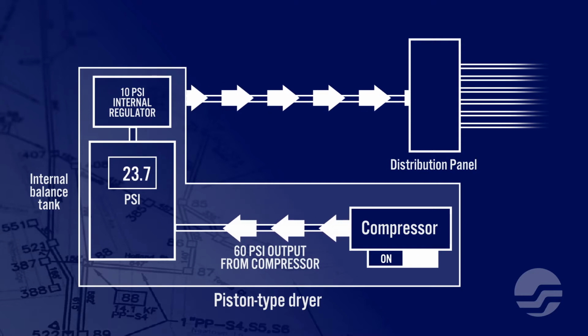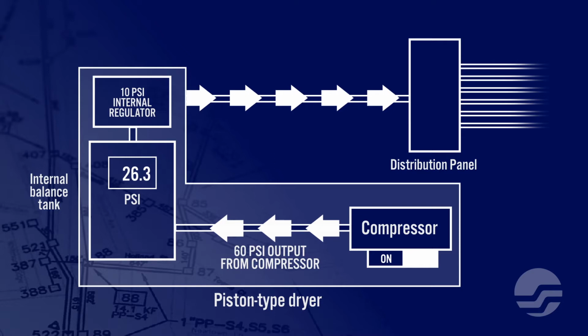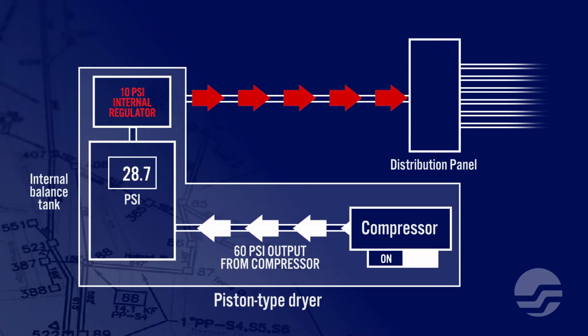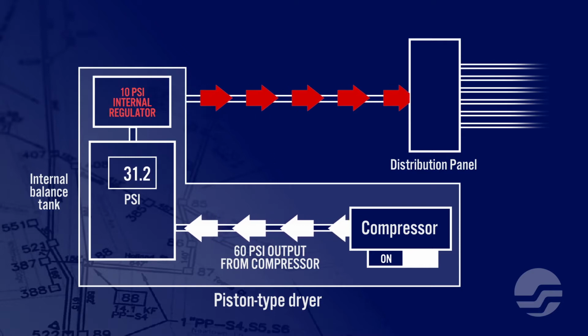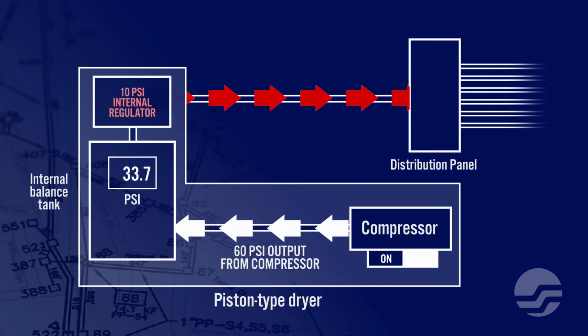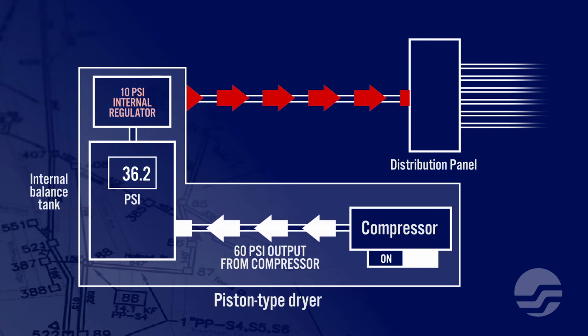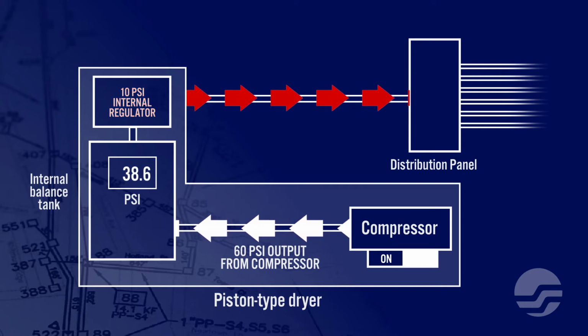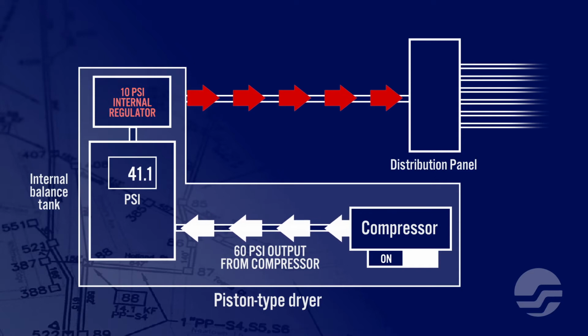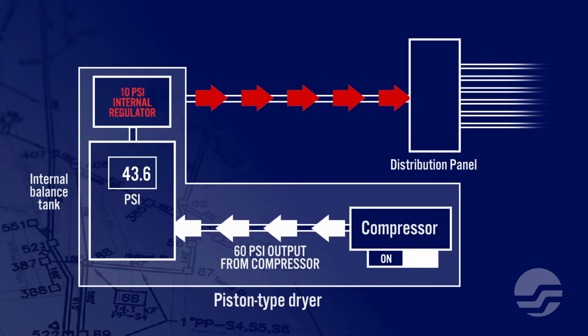While the pressure in the balance tank is rising, many regulators will have difficulty maintaining a constant 10 psi of output. Even an imperceptible increase in output pressure can cause a measurable increase in airflow through the flow measurement assembly. This increase in flow can cause a false alarm when no real alarm is warranted.